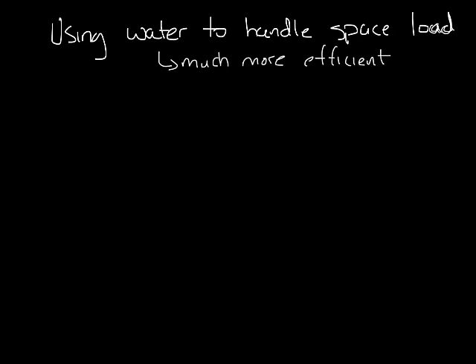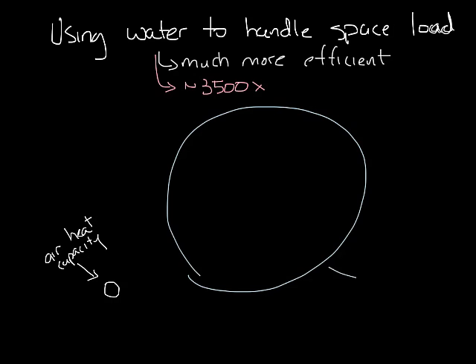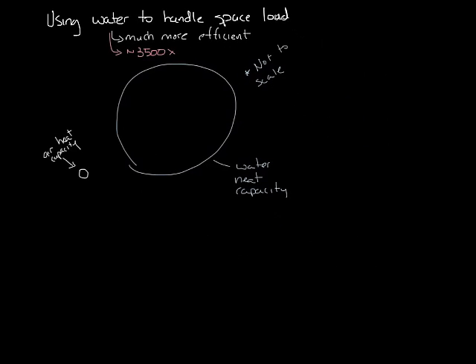Water is almost 3,500 times as efficient when it comes to heat transfer compared to air. Think of it like this: if a specific volume of air can transfer this much energy, then the same volume of water can transfer this much energy. Now, it's probably not to scale, but you get the picture. Let's make a little room here. Stated another way, a 1-inch water pipe transports the same heating and cooling capacities as an 18 by 18-inch ductwork.